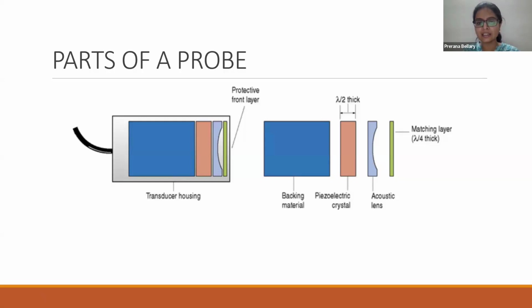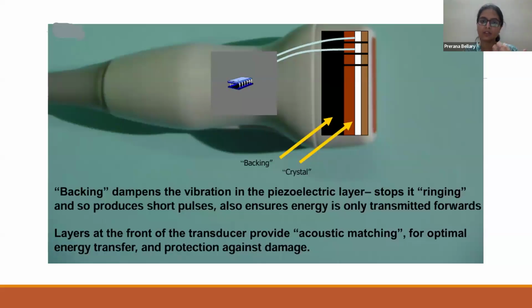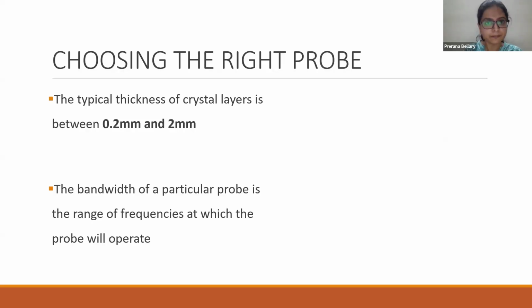What the backing material does is that it prevents stray vibrations, and it makes sure that the waves are transmitted ahead. It is made of an acoustic damping substance, and so it damps all the unnecessary vibrations. It stops the ringing, produces shorter pulses, and makes sure that the energy gets transmitted only forwards. Acoustic matching is done for optimal energy transfer, and it also protects against damage. This whole thing is covered by a protective casing.